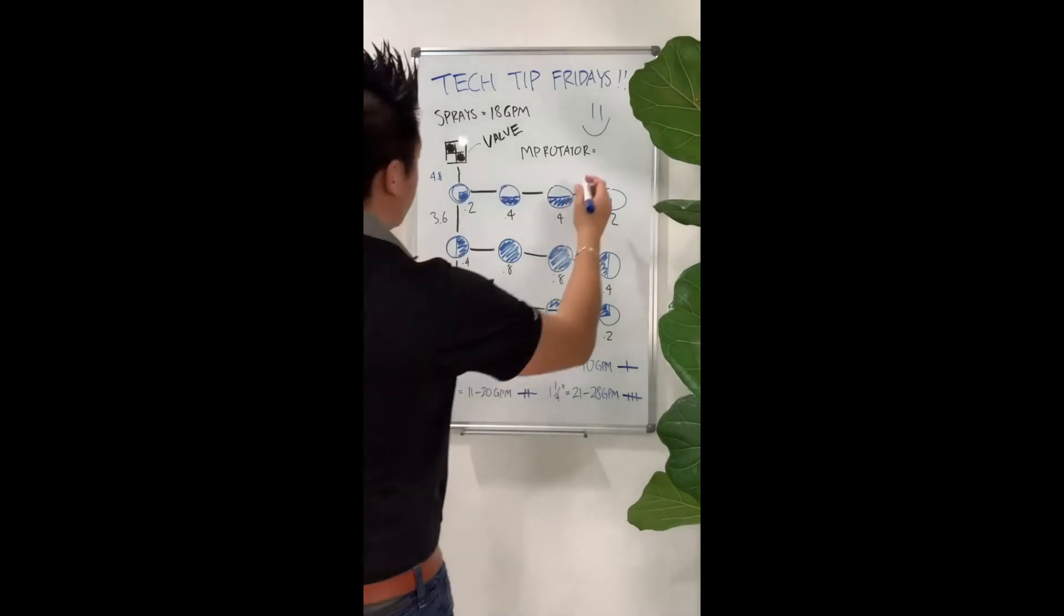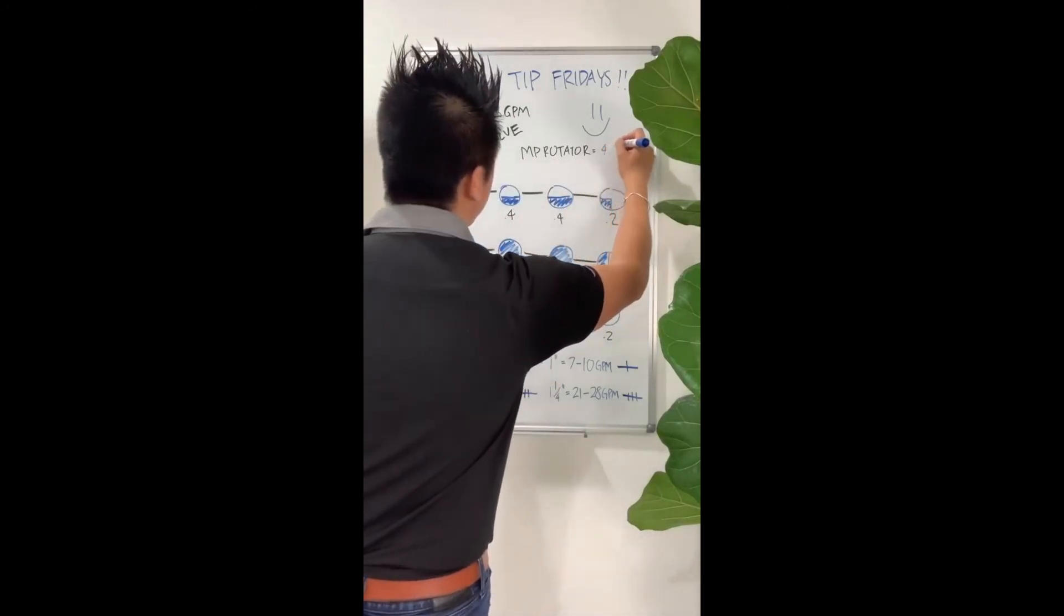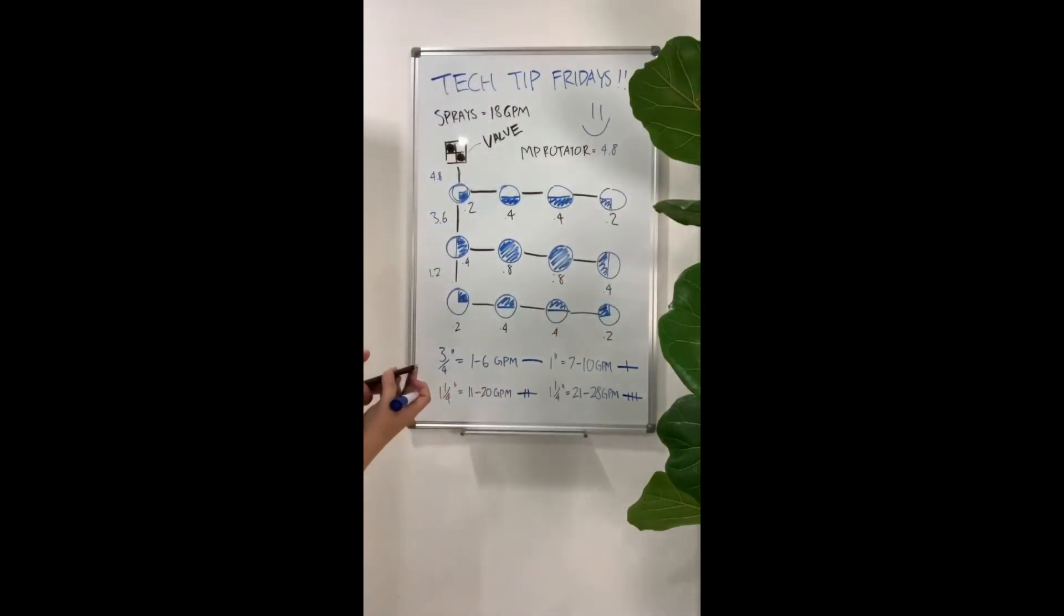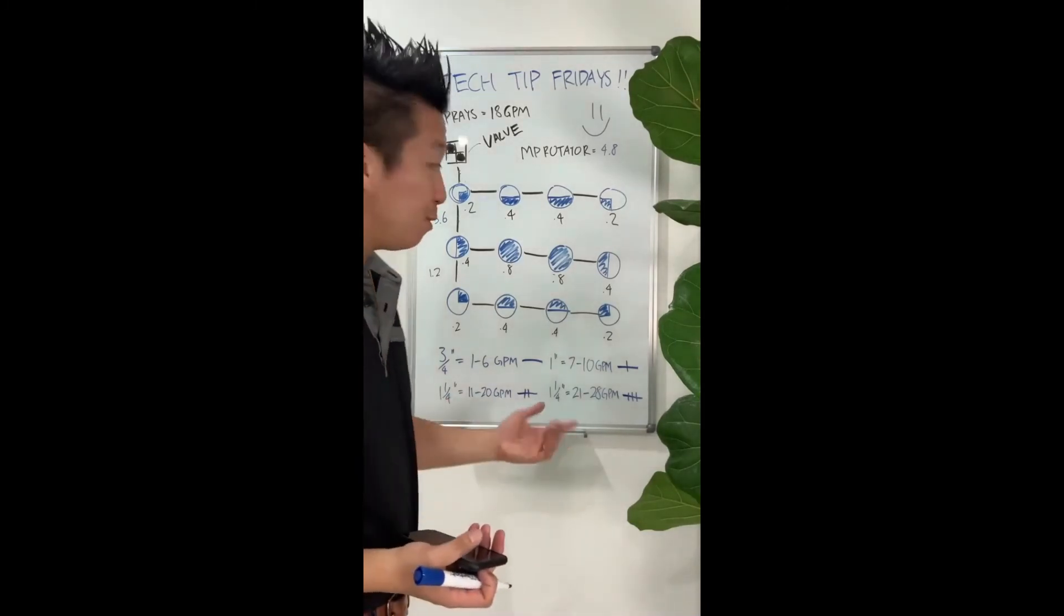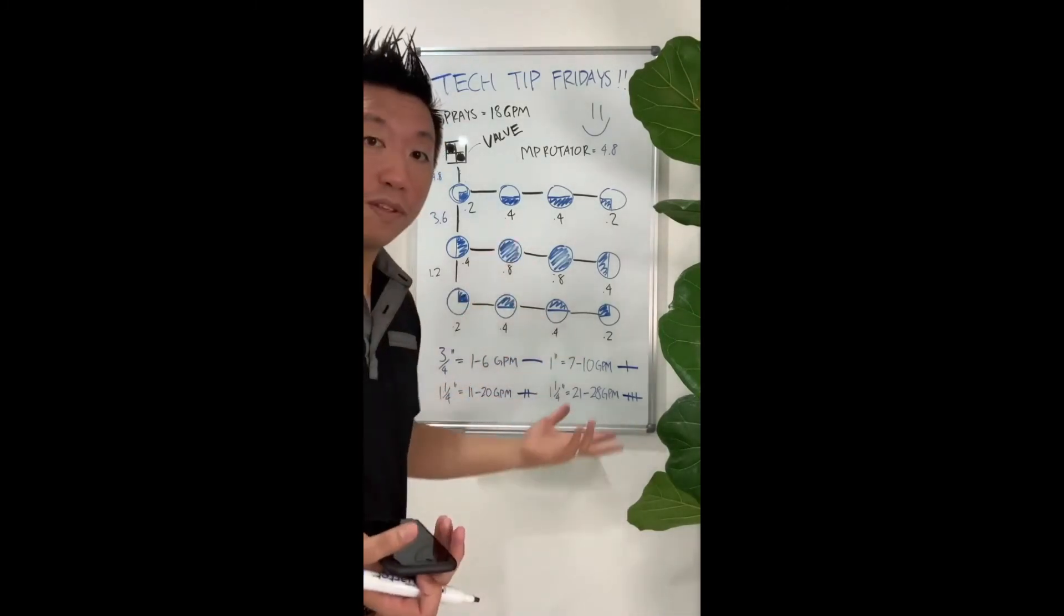Now with MP rotators, we have reduced the flow to about 4.8. And when you're looking at what size pipe you're going to use, 4.8 actually lands between 1 to 6 GPMs, which gives you a 3 quarter inch pipe. So if you're doing MP rotators, you can actually do 3 quarter inch pipe for the entire zone.